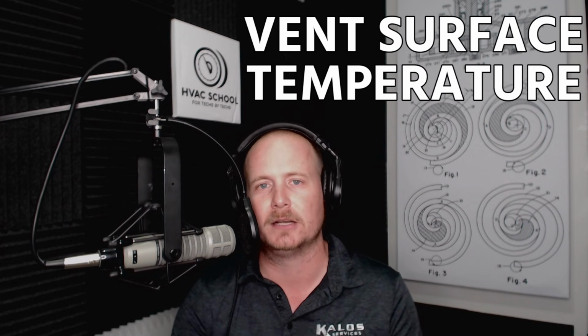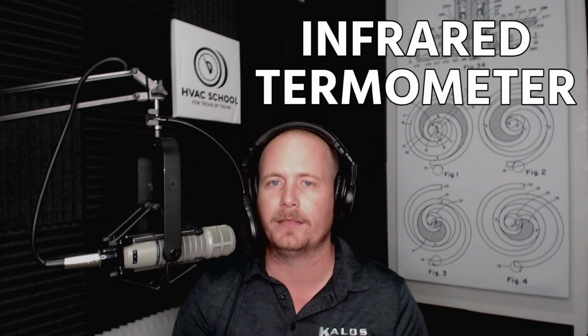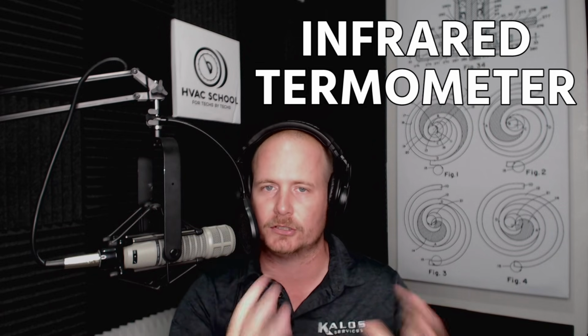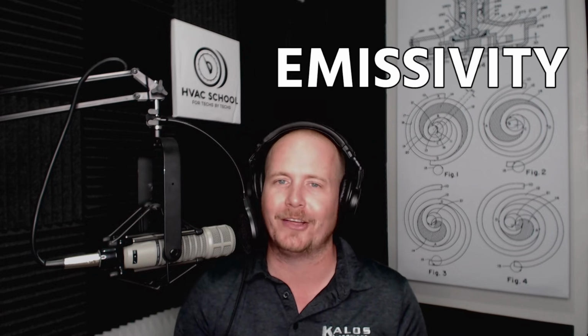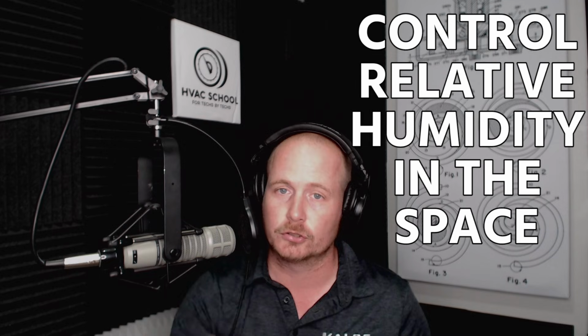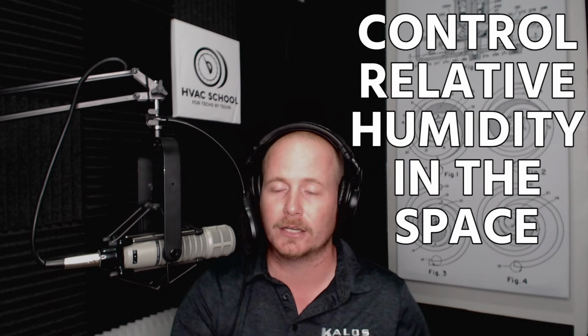Now that can be tricky to measure. Sometimes you can use an infrared thermometer if you get right up against it to measure the surface temperature of that vent. But now you have to know a little bit about emissivity and all that, and you have to know how to properly use infrared or thermal imaging. And that's another skill that you can't just jump into. You have to understand how that works, otherwise you'll get incorrect readings. But again, what we have to do is either control the temperature of the vent or control that relative humidity in the space, and generally controlling the relative humidity in the space is your best bet.